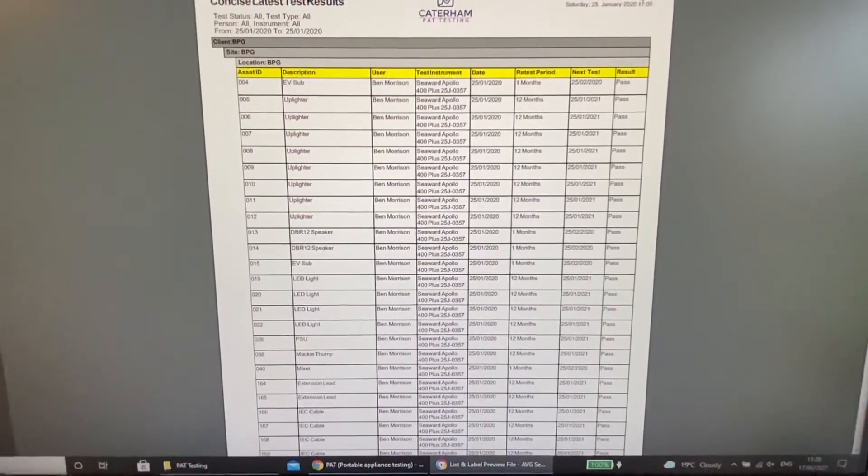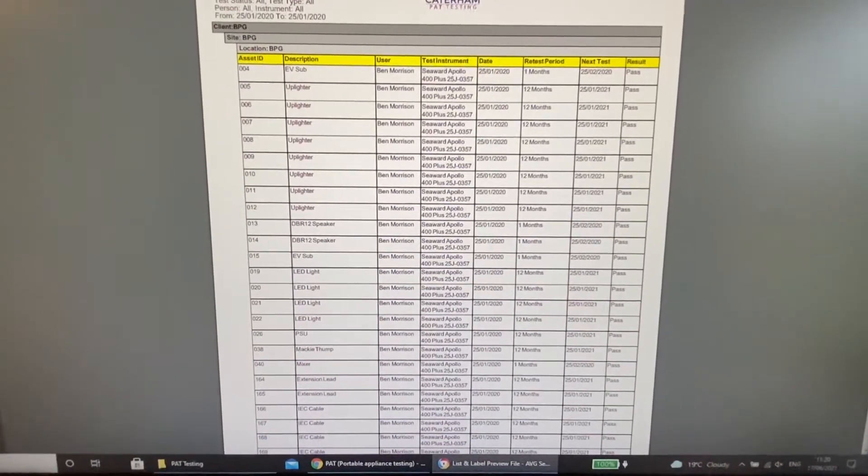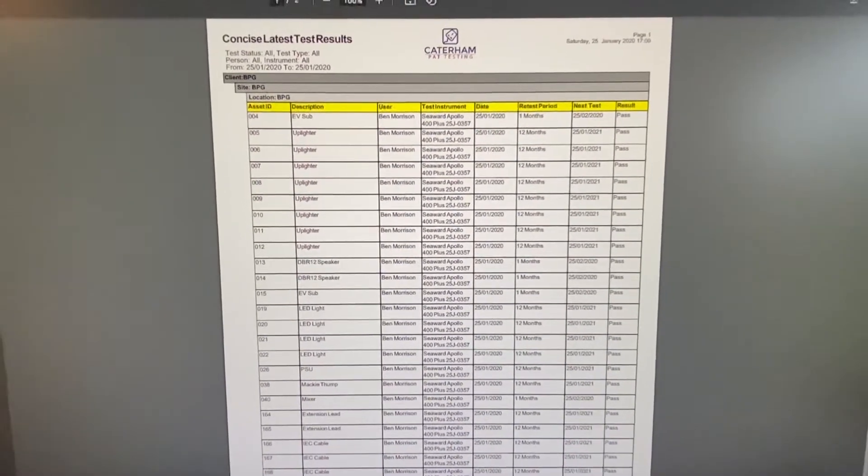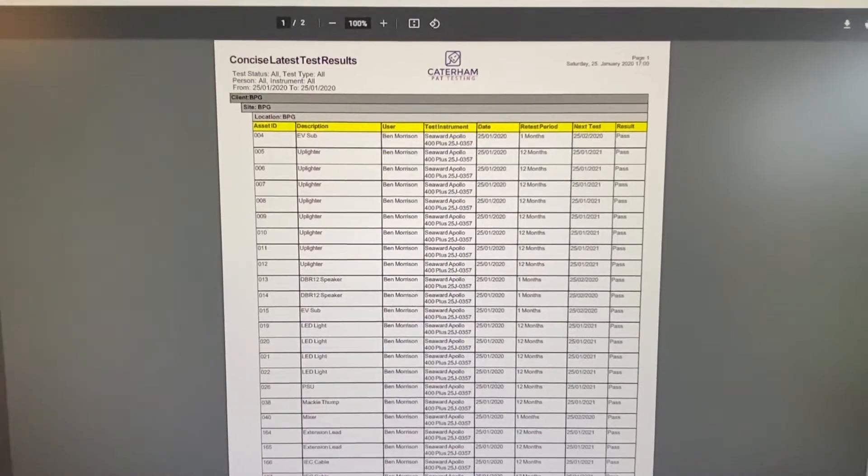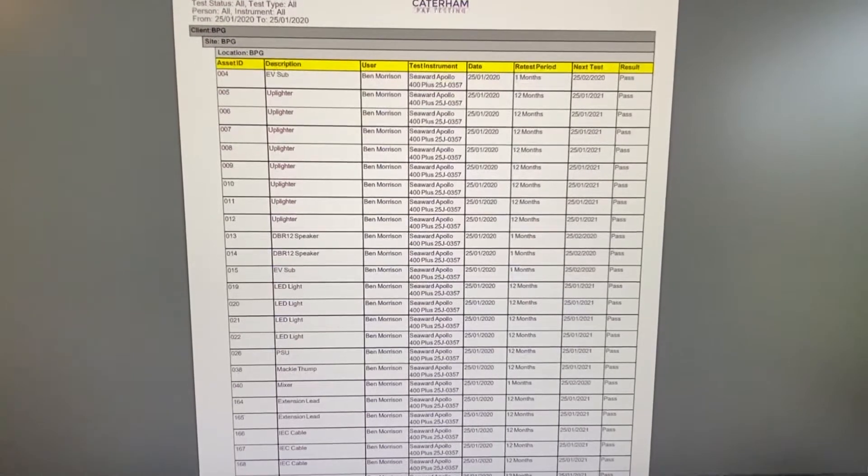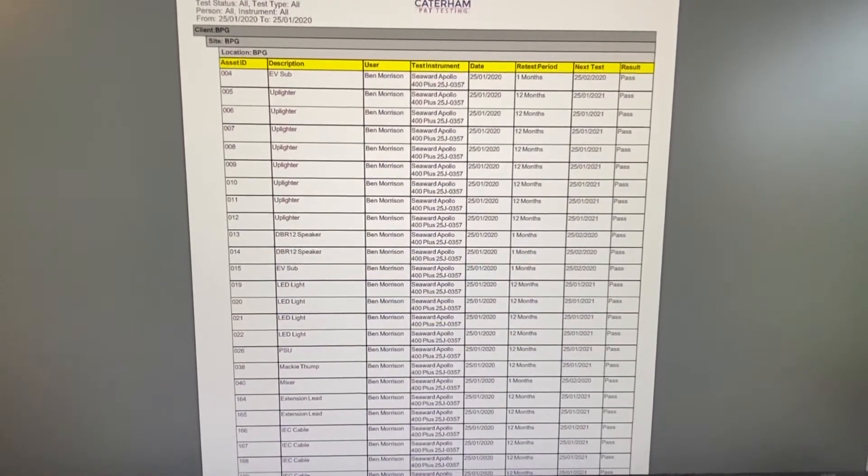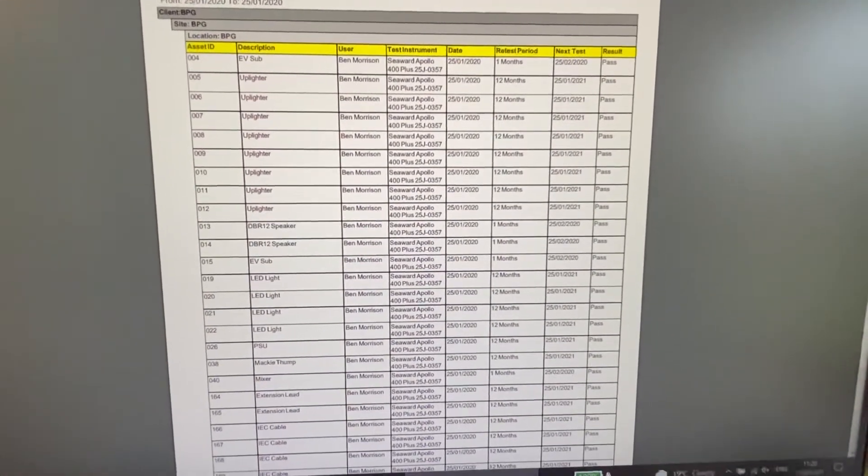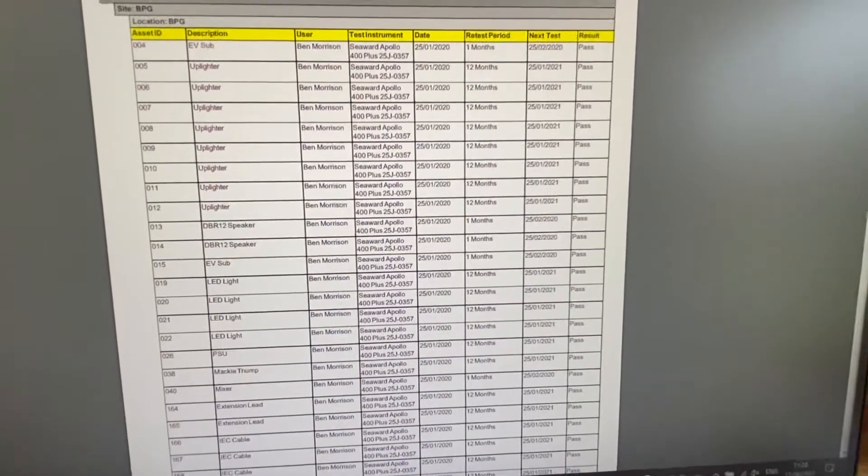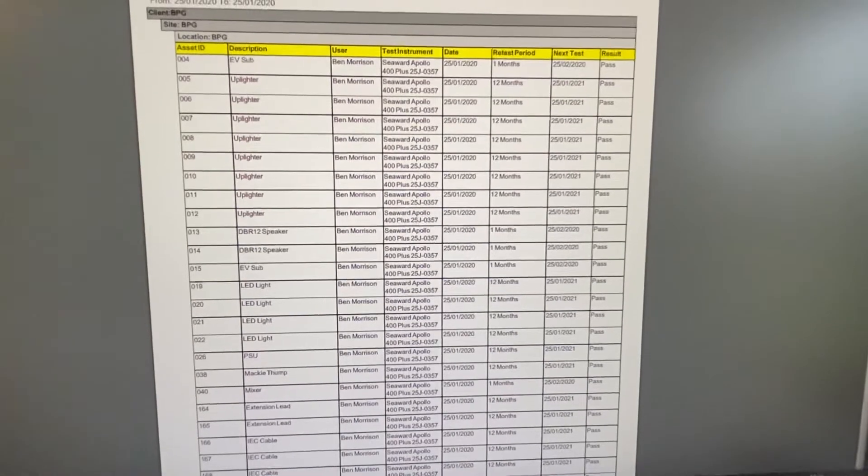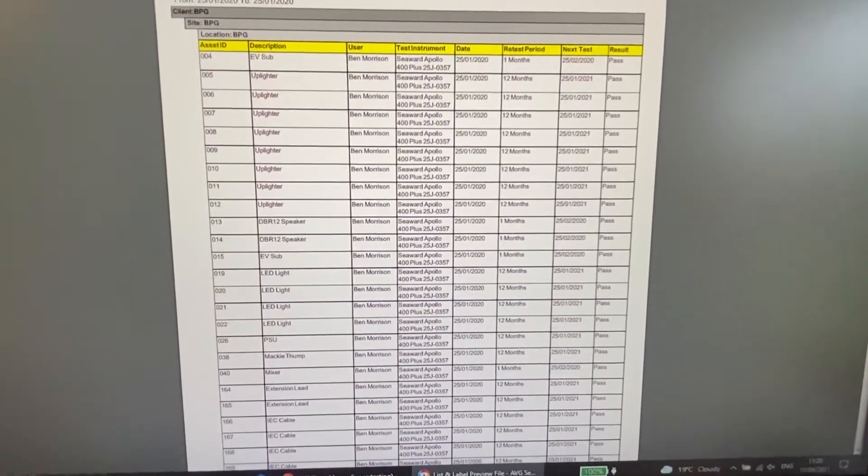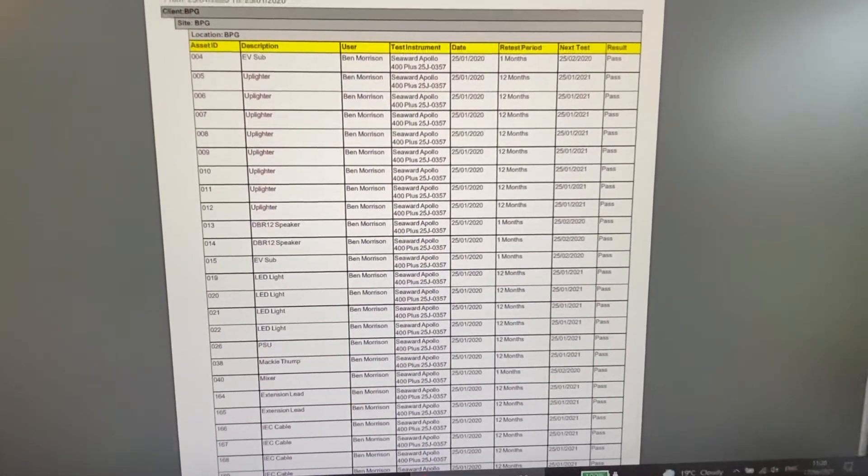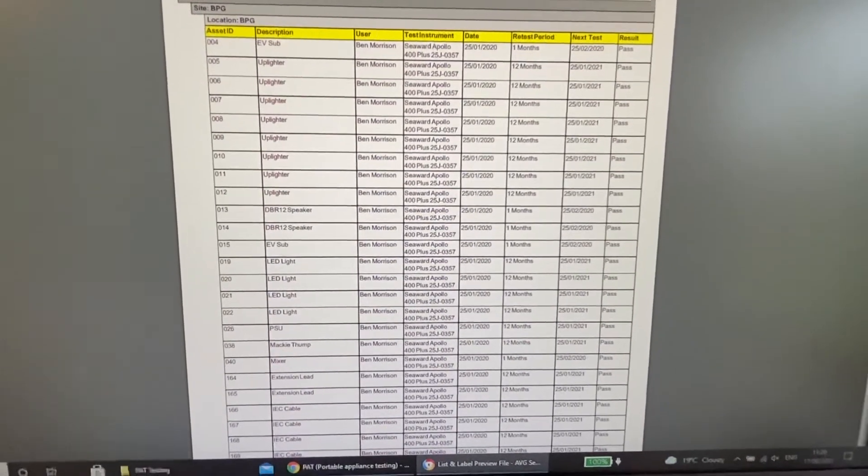There is a cost involved, but this gives a lot of predefined reports, as you can see here. So this is like a concise list. You can personalise it at the top with your logo, and it has the date and the time. And it basically here gives you an asset list for asset IDs, descriptions, the date it was tested and the retest period. So you can change that on the machine. I've got various ones here. And then it will give you a next test date. And obviously there's a lot of discussion about the next test dates. And in the recent code of practice, that's now down to the duty holder to decide how often you want that tested.